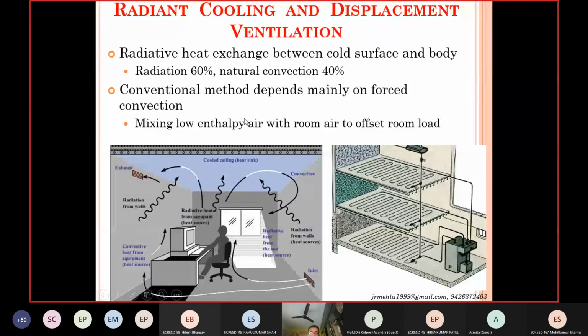So one of the technologies proposed, which is considered to be more energy efficient, is radiant cooling, right? It may be combined with displacement ventilation or an underfloor air distribution system. Okay, so the radiative heat exchange. The conventional cooling that is provided is mainly by the mode of convection. That is, the air is forced into the conditioned space, and let's say it's for human comfort. Then we also have the breeze of air passing over our body, and that's how our body also gets cooled, and the other objects in the conditioned space also get cooled.